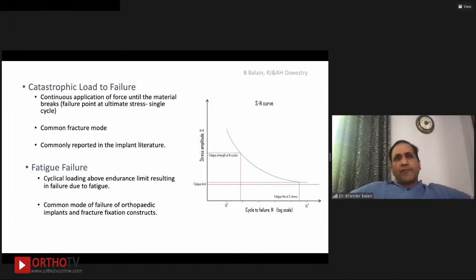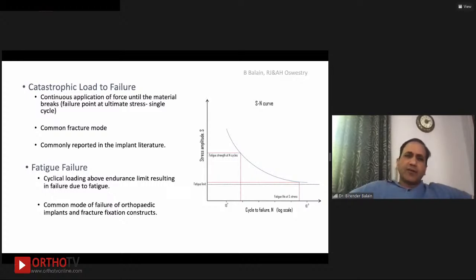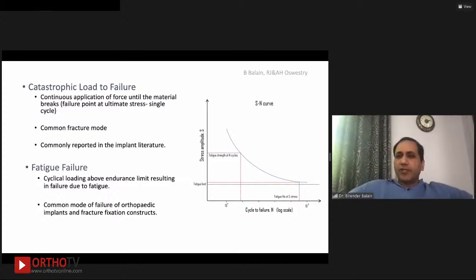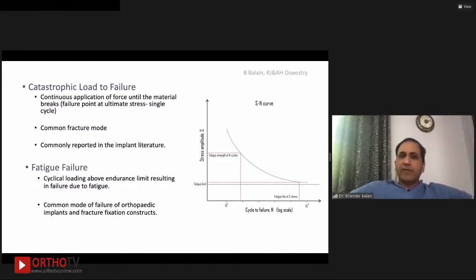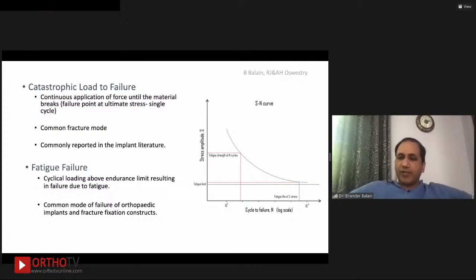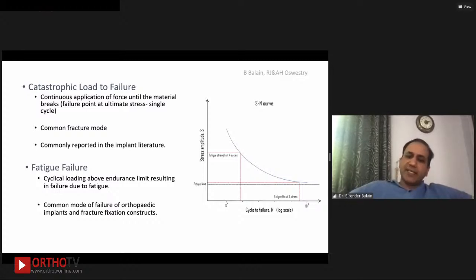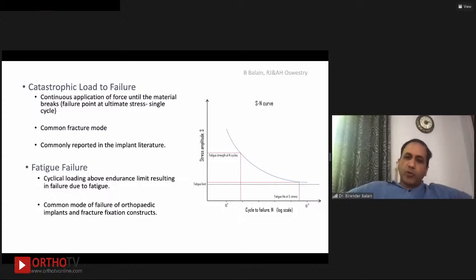Looking at materials and their stress-strain curves, cobalt chrome and stainless steel have very high elastic modulus. Titanium is roughly half of those, and cortical bone is far less than titanium. That is why we use titanium — its modulus of elasticity is closer to bone than other metals. There are two modes of failure to understand: implants can fail from a single catastrophic load, as commonly reported in literature, but in life most implants fail by fatigue rather than a single external force. Fatigue failure depends on the endurance limit of the material and is the common mode of failure of orthopedic implants and pedicle screw fixation constructs.